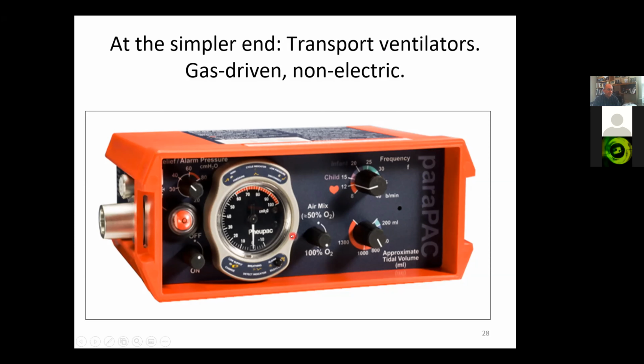It has its taper fitting to the patient connecting tubing here, but what you can't see is that in back, it has the proper screw-on fittings for high pressure oxygen and nothing else. There's no electric cord, there's no medical air under pressure screw-on fitting. So this entire thing gets its controlling power from the gas pressure only, and all of the switching is done mechanically. The change from inspiratory phase to expiratory phase, the timing between those, the time ratio between them, all of it. And what you'll notice here, pay a bit of attention to this one.